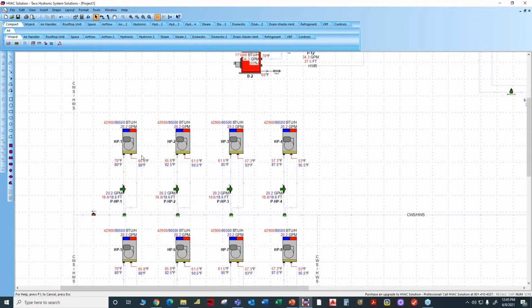And the nice feature about this system is that this particular heat pump number 1, for example, could be in the cooling mode, and heat pump number 2 could be in the heating mode. So you could have simultaneous heating and cooling in this type of system. So this is not a changeover. You get simultaneous heating and cooling.